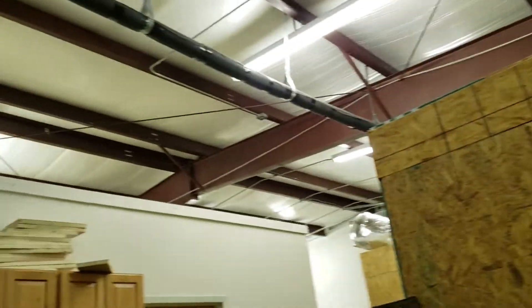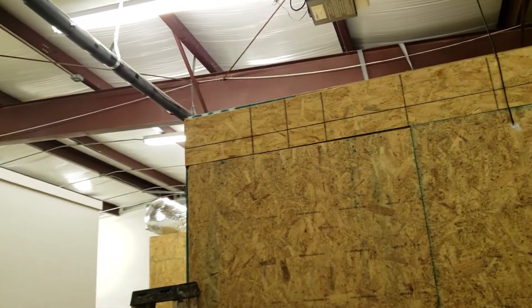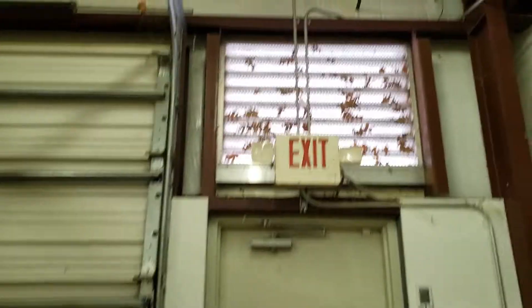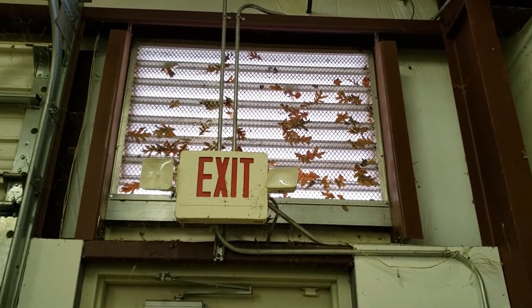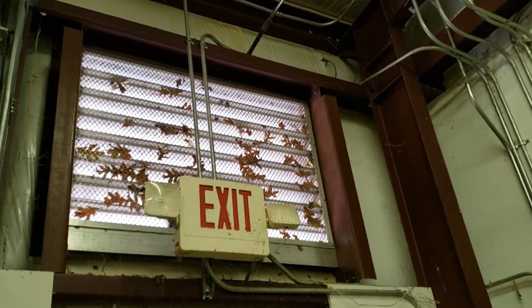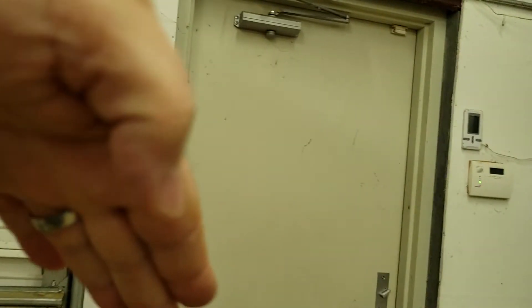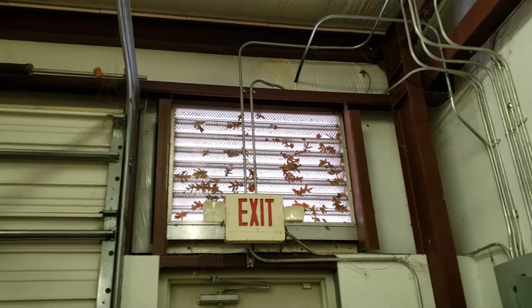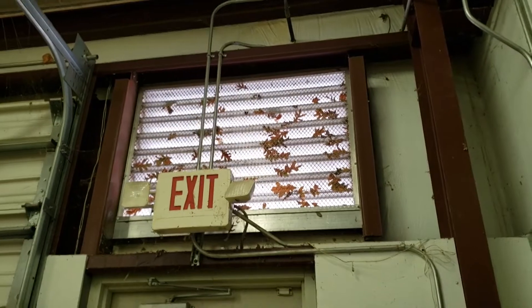Air intake for this facility: the air comes in and cycles around the interior, so it is important to have a decent air volume. This place looks pretty large but you're going to want about three times the size of your server center just for air volume, so it has a mixing location. The air is coming in at this location through what's kind of like a drip ledge screen. Essentially, there's a flange done at an angle with a drip edge. When it's raining and pulling in the air, it hits that edge and gravity pulls the water all the way down while the air continues up. This has worked flawlessly — we've had major thunderstorms without any water coming in whatsoever.